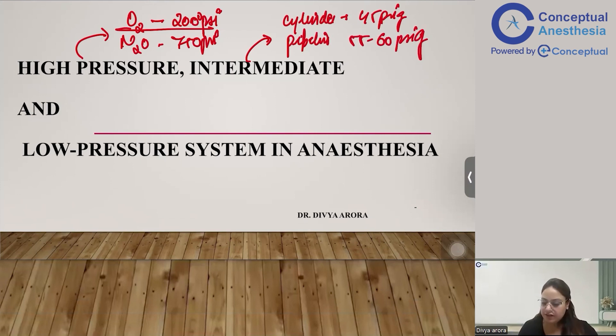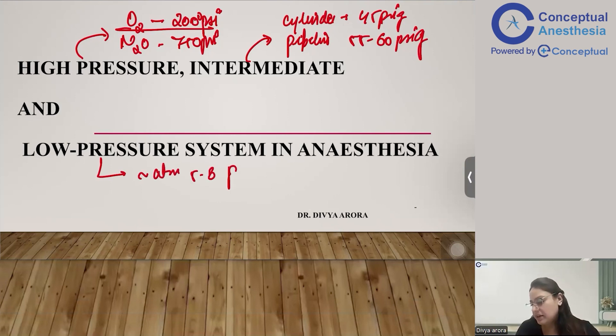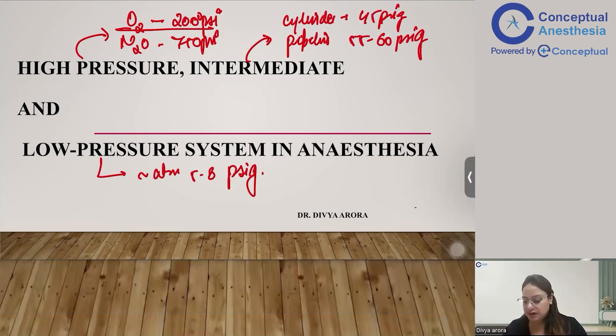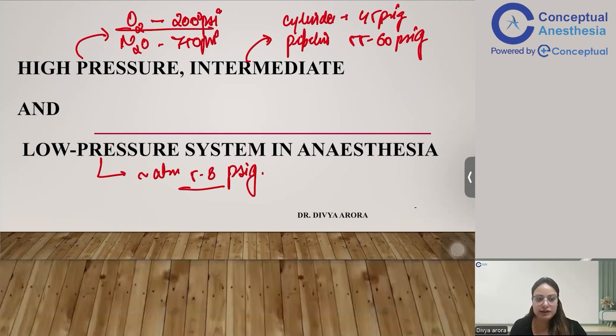The low pressure system is approximately at atmospheric pressure, around 5 to 8 psig. So to summarize: high pressure is the oxygen cylinder at 2000 psi and nitrous at 750 psi; intermediate is 45 psig for cylinders and 55 to 60 psig for pipelines; and low pressure is less than 10, specifically 5 to 8 psig.